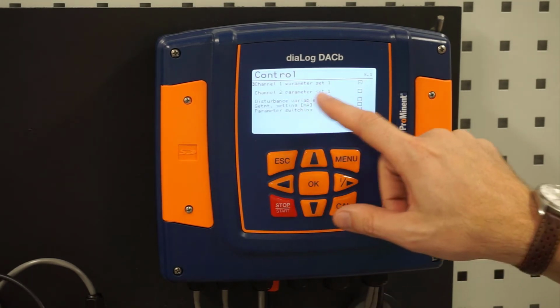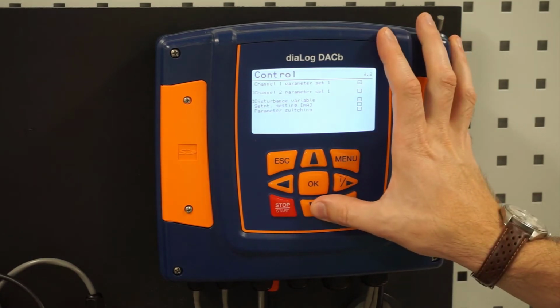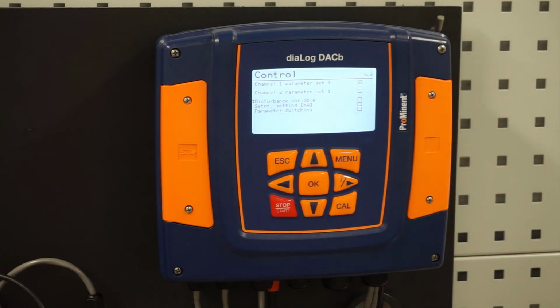We could also do that for channel 2. If we have a disturbance variable, that would be our water meter. We would go in there and set that water meter up to add that additional variable to affect our control. With that water meter, we can get much tighter control over a process if it is set up correctly.